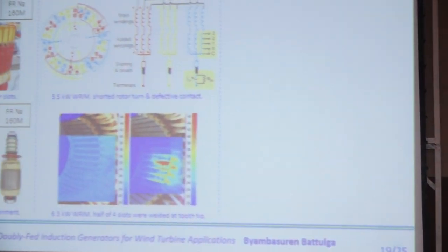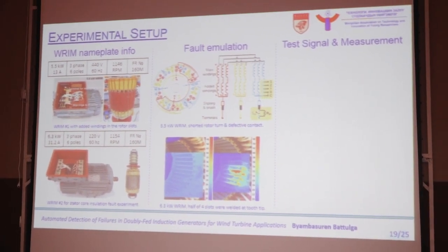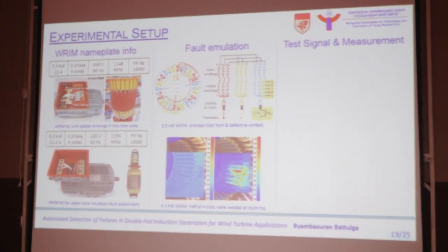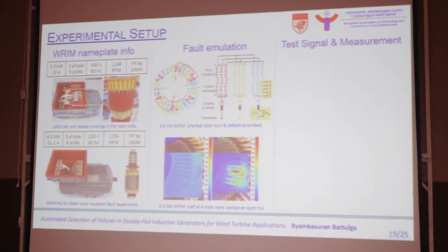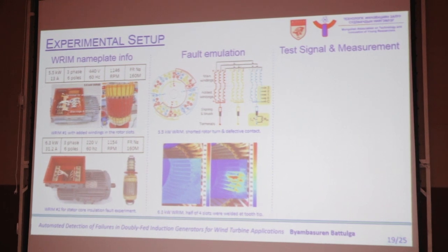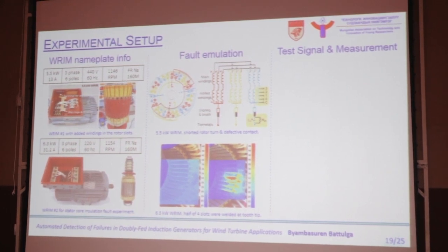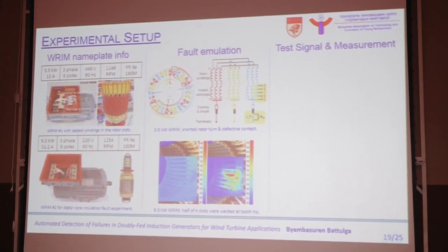In the top, the defective contacts were emulated by connecting a series resistor to one phase, which is about 11% increase. And shorting adjacent turns in the random winding is a very difficult task. Therefore, the same number of coils were added to each phase to control fault level from 0 to 3 shorted turns, as shown in the circuit diagram in the top second column.